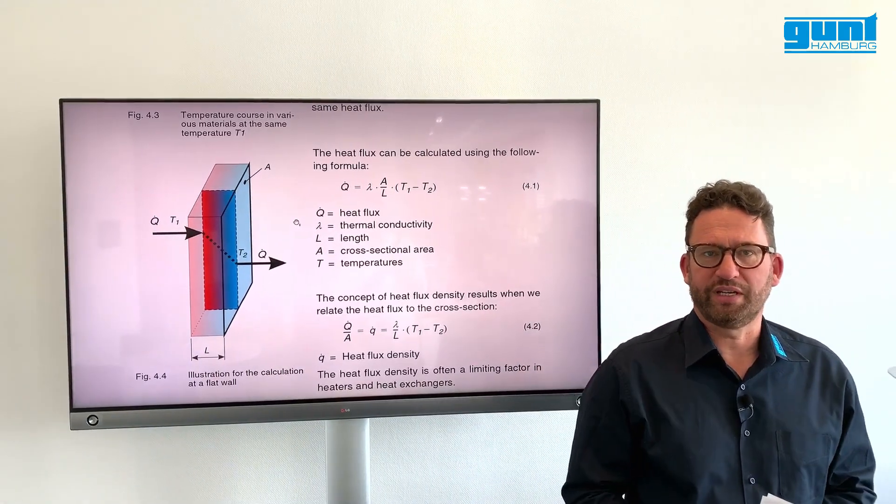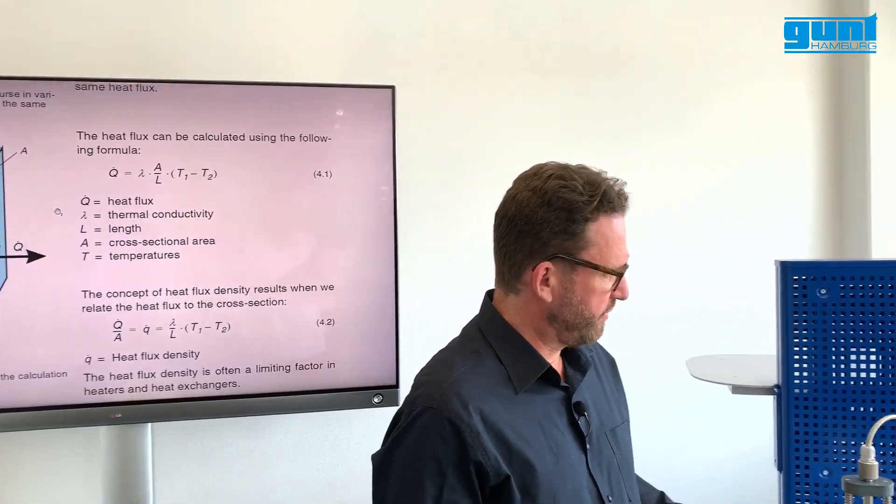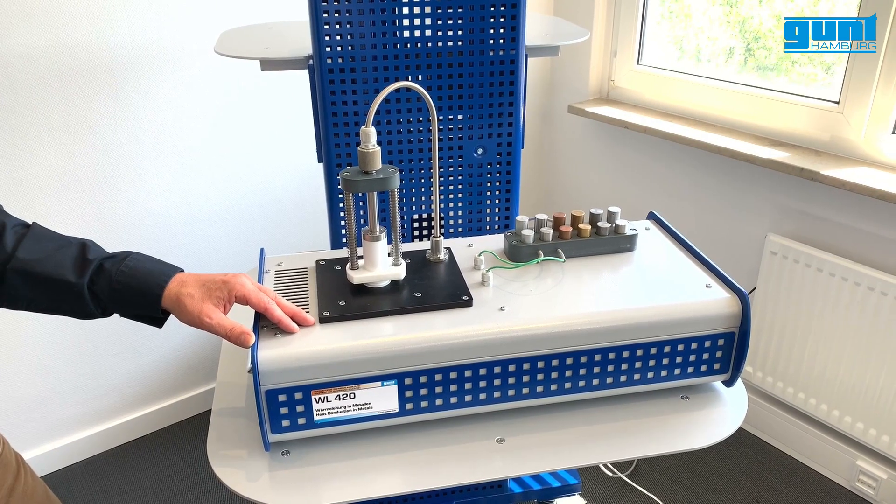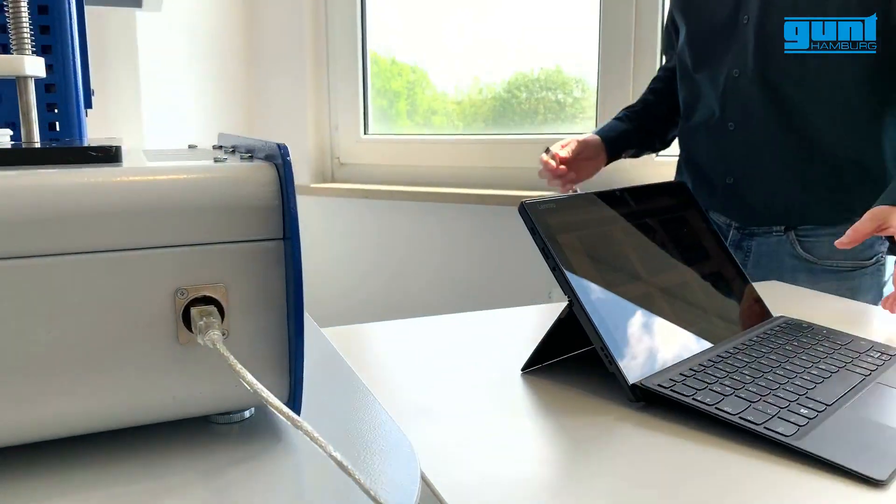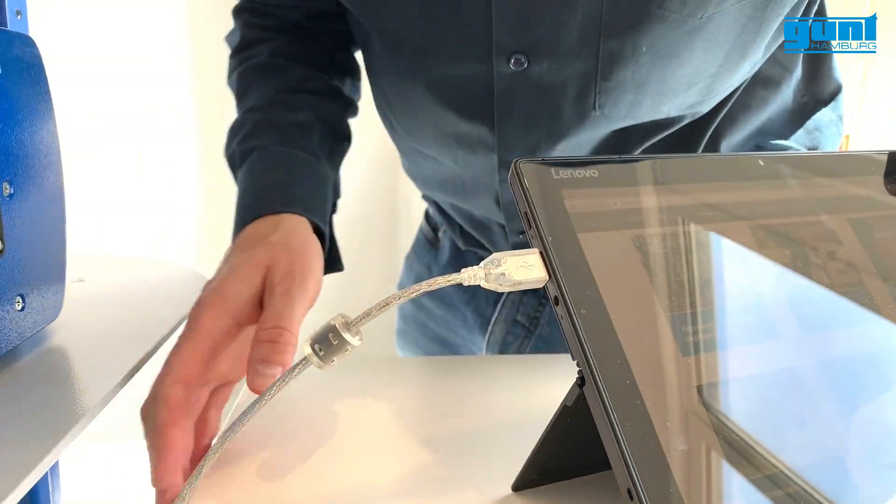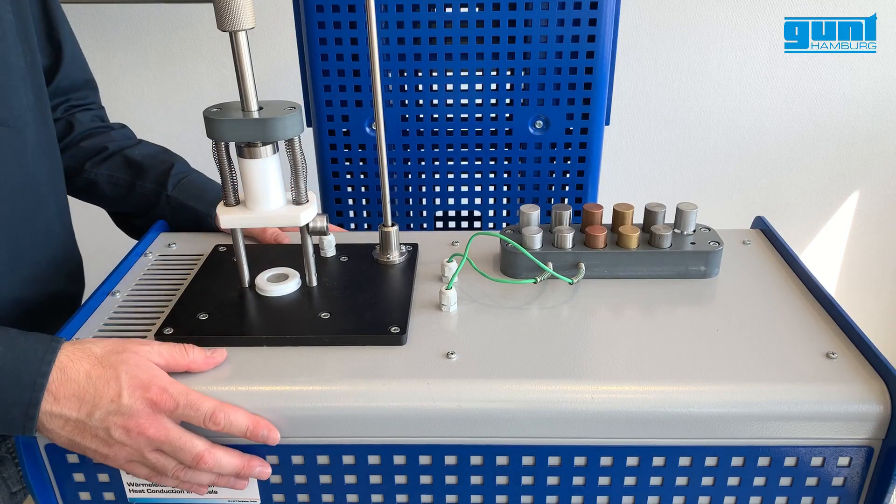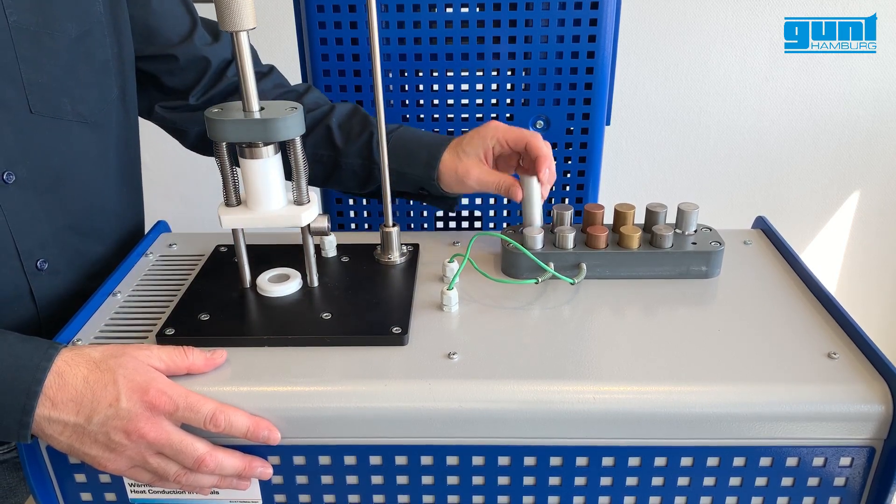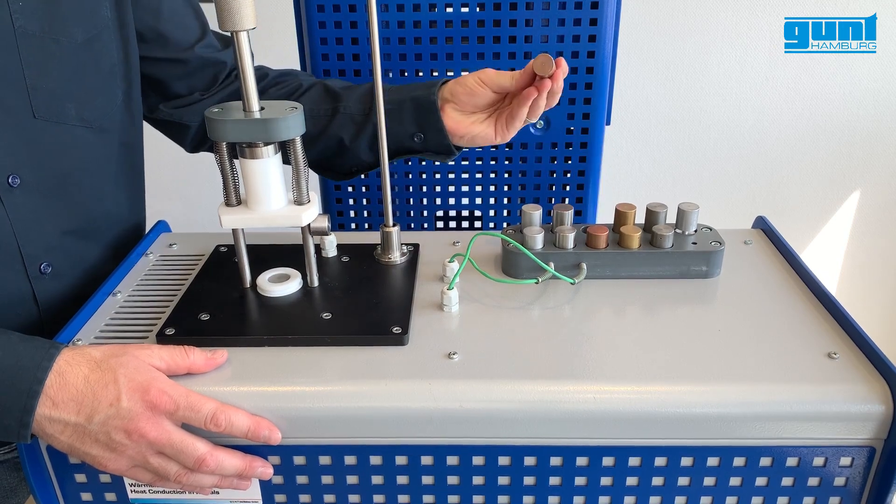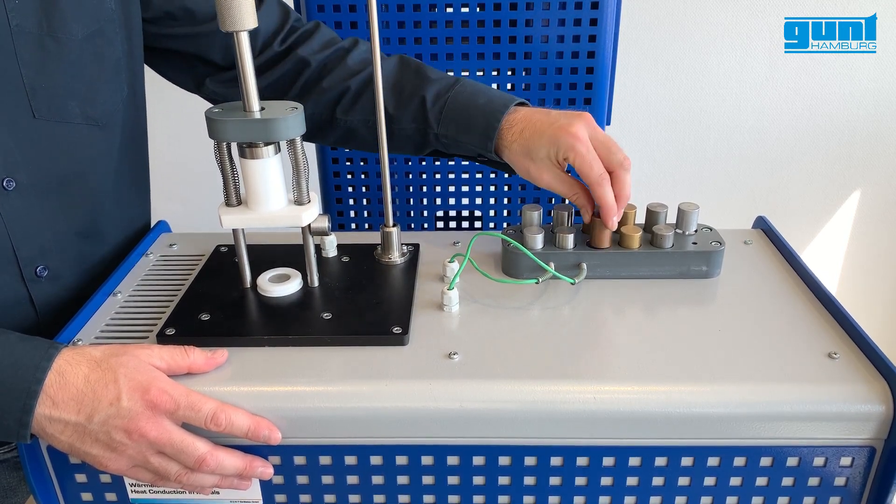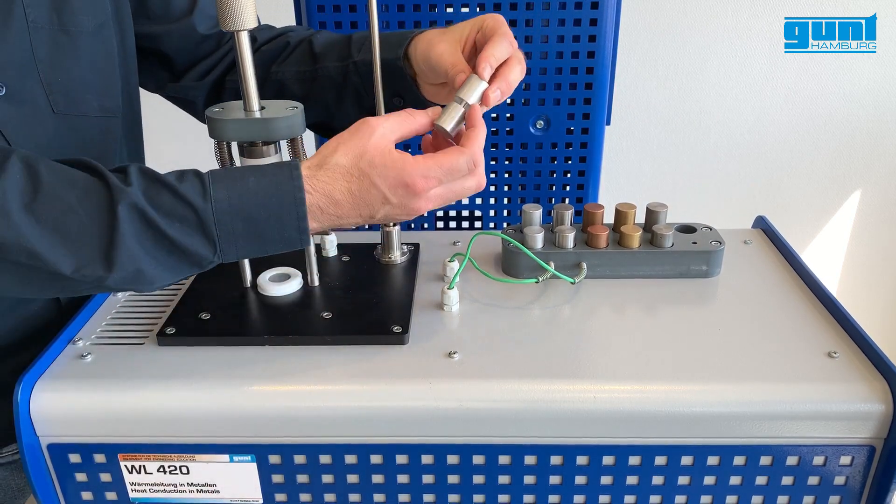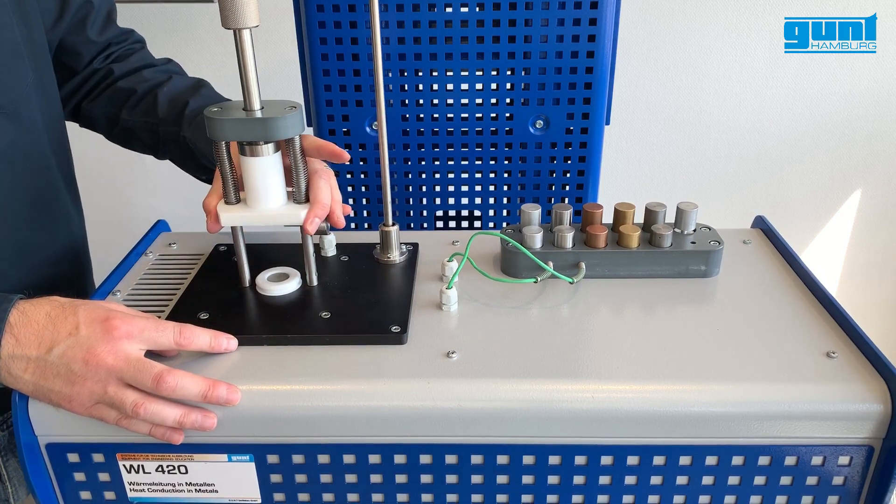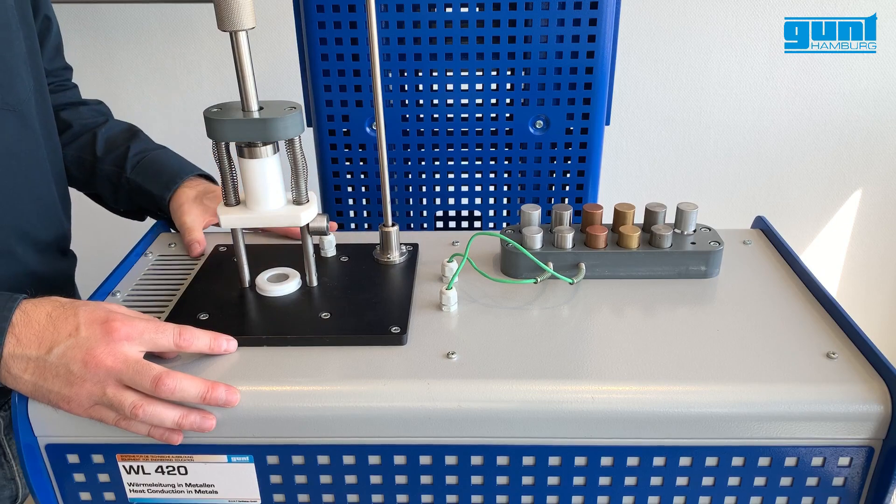The WL420 is designed as a benchtop unit. Here we have the base which contains all the electronics necessary for the sensors and the connectivity to the PC with the Gunt data acquisition software. It is important to point out that the PC is necessary. The actual experiment is located on top of the base and happening here on the left. The WL420 comes with specimens for five different materials and two different lengths respectively, as well as one specimen with constricted cross-section. The specimen is placed in this spring-loaded device which ensures reliable contact of all heat transferring surfaces.